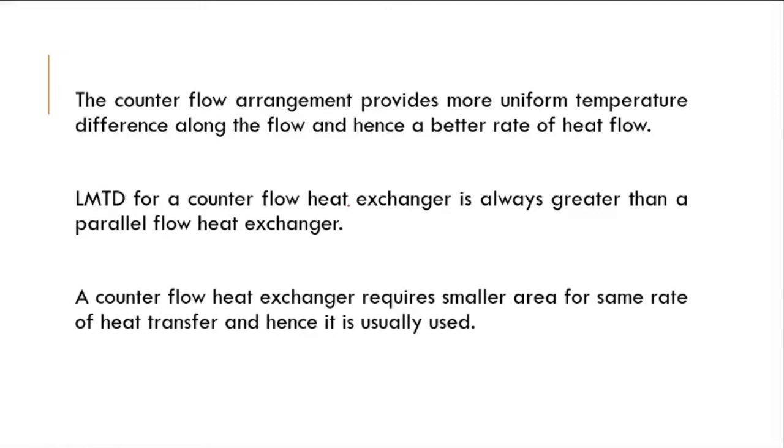Now, since LMTD for counter flow will be greater, the area requirement will be smaller for a counter flow heat exchanger. Since the area requirement is less, we will be using less material for it, and hence using a counter flow heat exchanger will be more economical. For the same rate of heat transfer, the area requirement will be low. Thus it will be more commonly used. It is usually used.